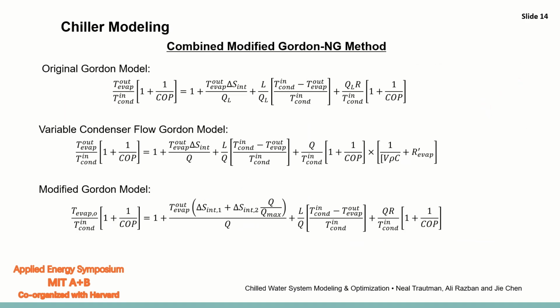And that brings us to our chiller modeling. We used combined modifications of the Gordon-Ng method. The original Gordon model is a thermodynamic relationship that ends up regressing variables that are hard to collect, including the internal entropy change, the rate of heat leaks to the environment, and the thermal resistance of the heat exchangers. We ended up incorporating two different modifications. The first incorporates variable condenser flow rate into the model. The second improves the model's accuracy for measuring the coefficient of performance for chillers equipped with variable frequency drives, such as the one we collected our data for.